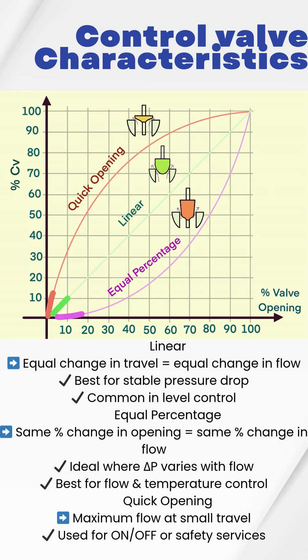Equal percentage characteristic gives equal percentage change in flow for valve travel. This is ideal for flow and temperature loops, where pressure drop varies with flow.